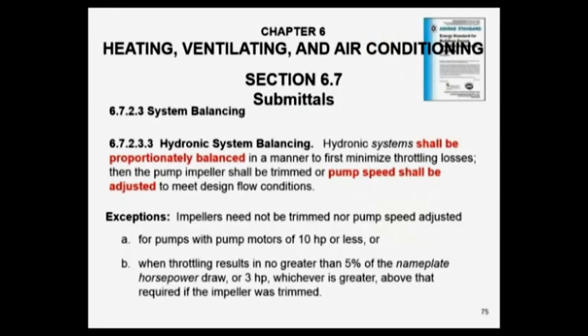Go back to our hydraulic balance statement here. Hydronic systems should be proportionally balanced in a manner to first minimize throttling losses, then the pump impeller shall be trimmed, or the pump speed shall be adjusted to meet design flow. What does all this mean?